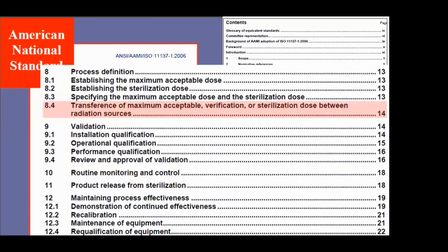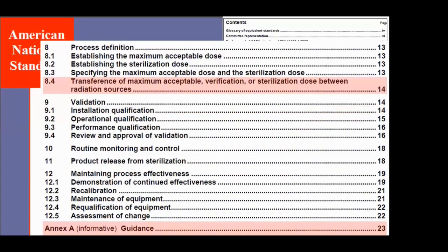It's right in the standard. You'll see, under process definition, where you're establishing the max acceptable dose, the doc talks about product qualification. To what dose have you qualified your product? What's your maximum acceptable dose? And establishing the sterilization dose. Right there, it speaks of this transference of dose. If you're going to move to a different radiation source, what is that? There's guidance in the standard.